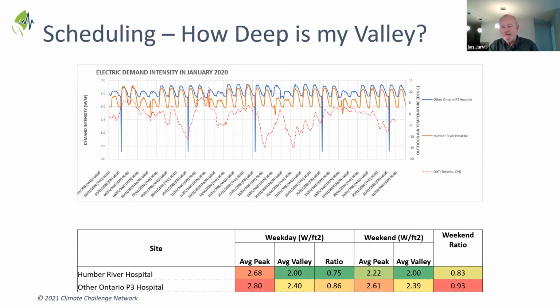To get really big reheat and heating savings, that's the base thermal, because you're not bringing in all kinds of outside air that has to be conditioned on the way through.